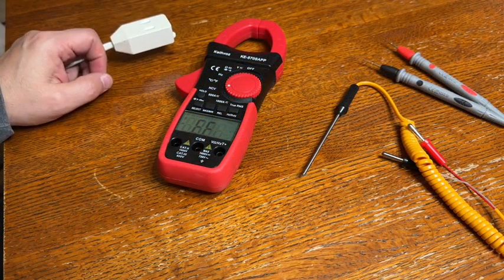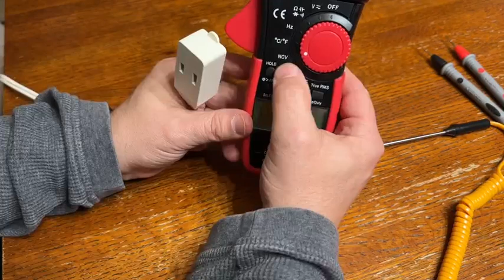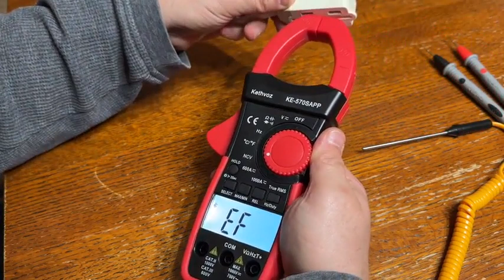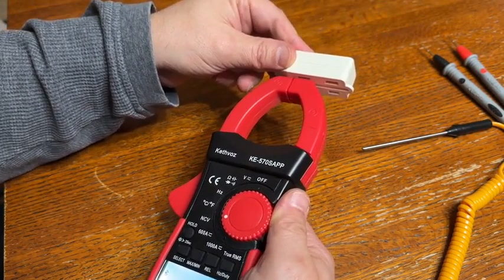In addition to using the probes and the clamp, which can open up to 45 millimeters, you also have another way of detecting current, and that is to use the NCV, which stands for non-contact voltage. I have an extension cord plugged in, and I'm going to turn my backlight on by pushing and holding. You can see EF. Now when I get this close to it, this is telling me that we have a live outlet. So that's one way you can safely approach any electrical wire or outlet and see if there's anything running to it before you do anything else.